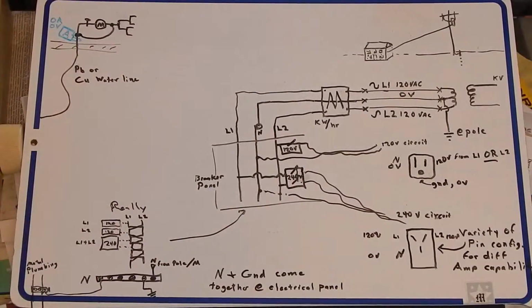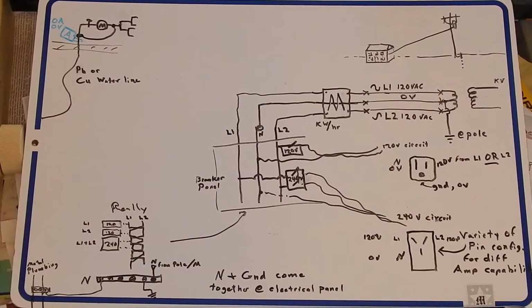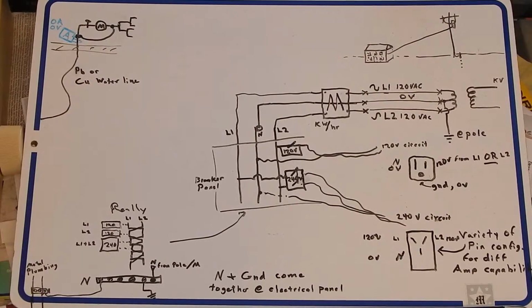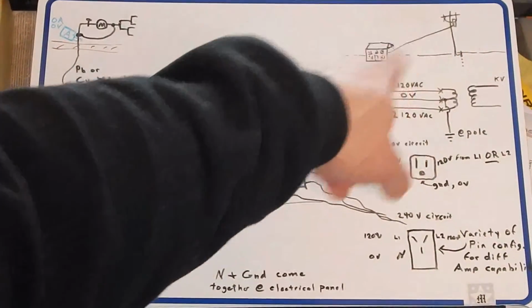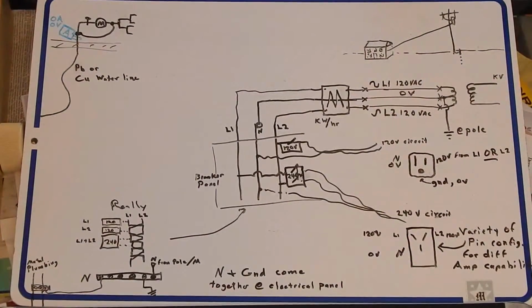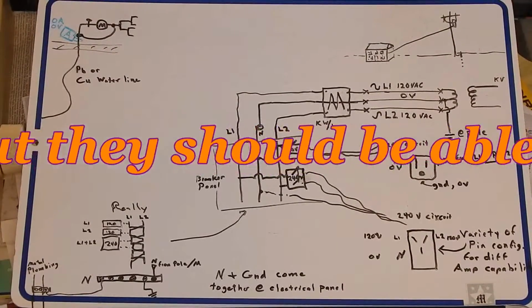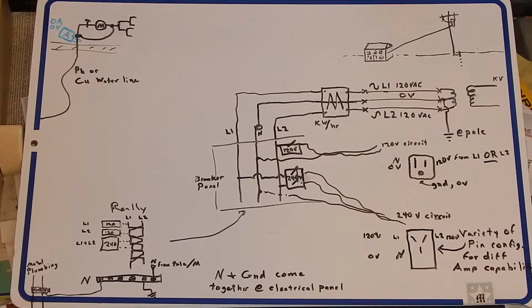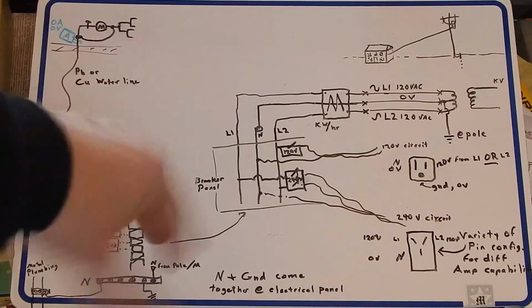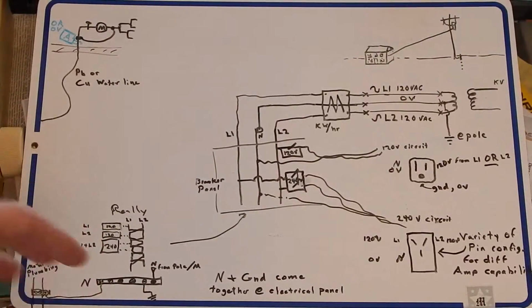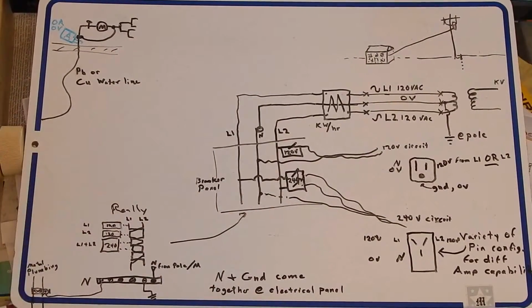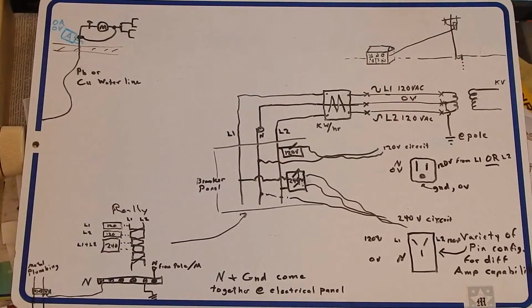If you do detect this condition where you've got some outlets high, some outlets low, then you need to get help immediately, ASAP. Depending on your electrical company, the service drop may or may not be the company's responsibility. It seems to vary in areas. But you just have to start making phone calls and find out what you have to do if you've got that situation going on. You don't want to use your wash machine, reaching into the water that's grounded, when your neutral is no longer grounded. You could really potentially be in a lot of trouble.